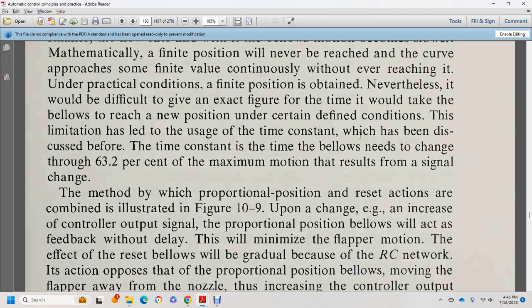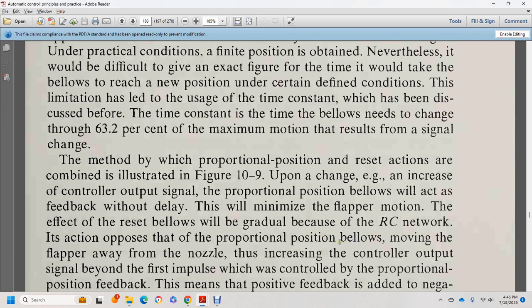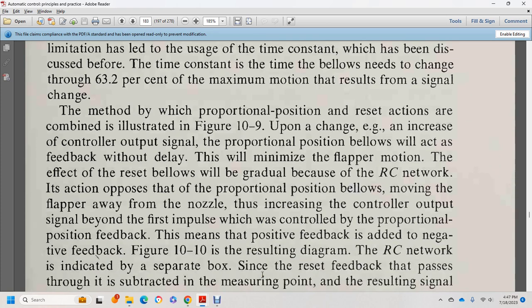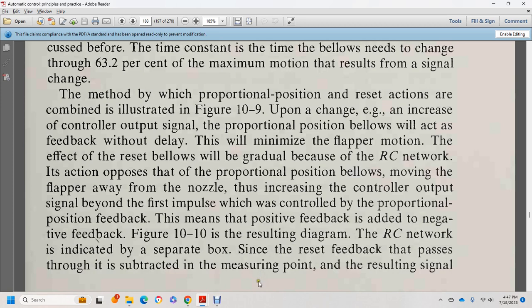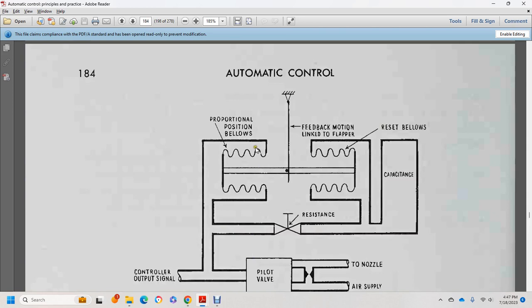Proportional position combined with reset action is illustrated in figure 10-9. Upon a change in the controller input, the proportional position bellows responds immediately without delay, but the reset bellows gradually recovers through the RC network. The reset action drives the flapper away from the nozzle, moving the control output signal beyond the value controlled by the proportional position feedback. Figure 10-10 shows the result — the RC network is indicated by a separate box providing negative feedback.